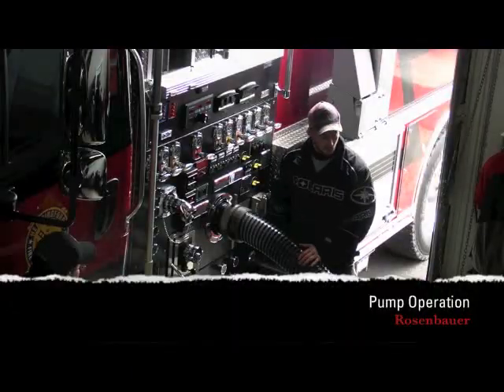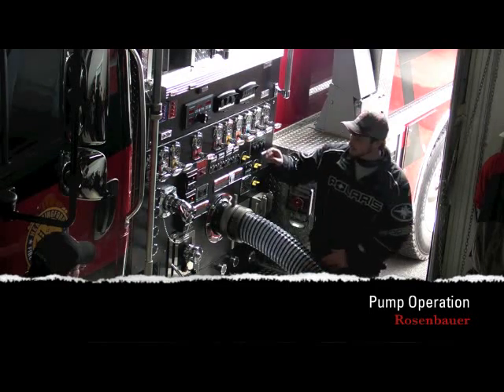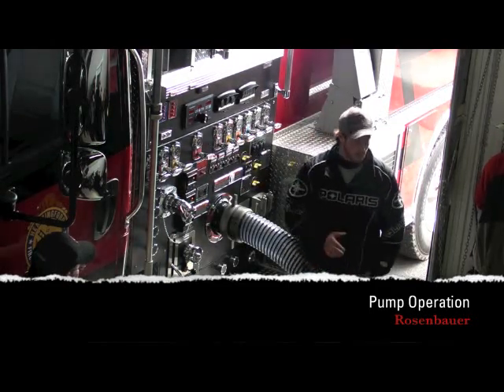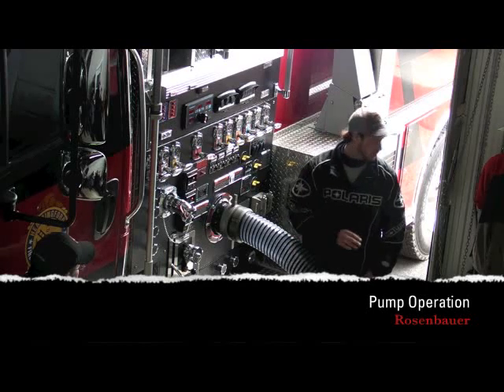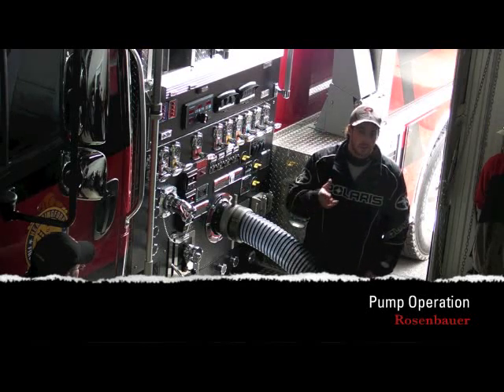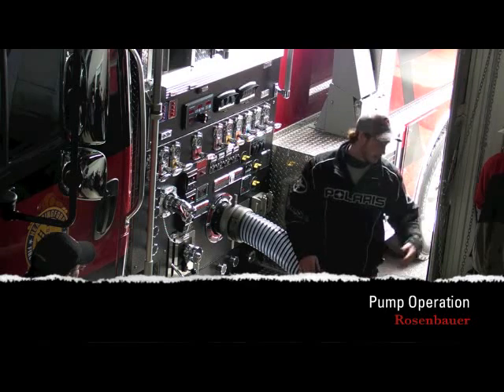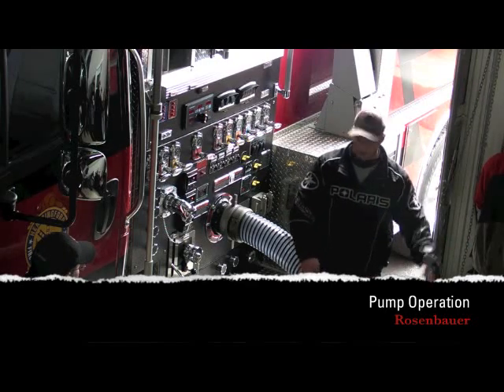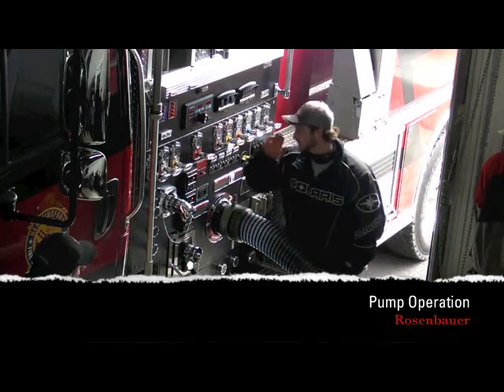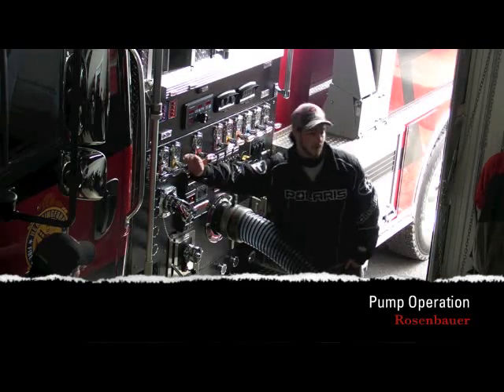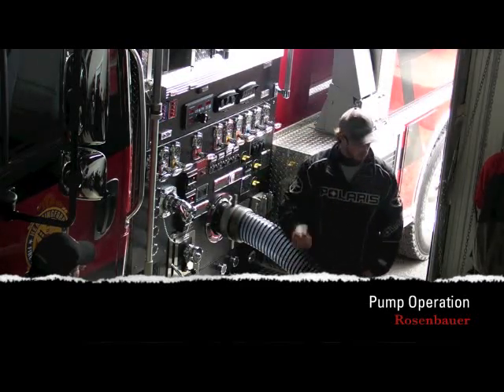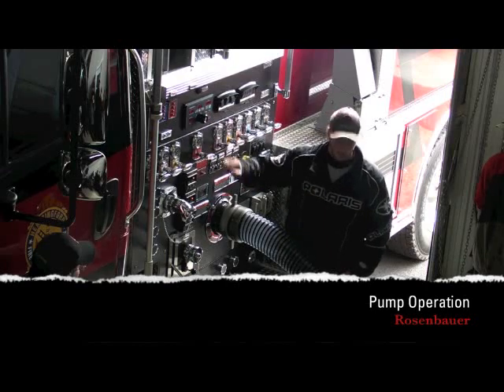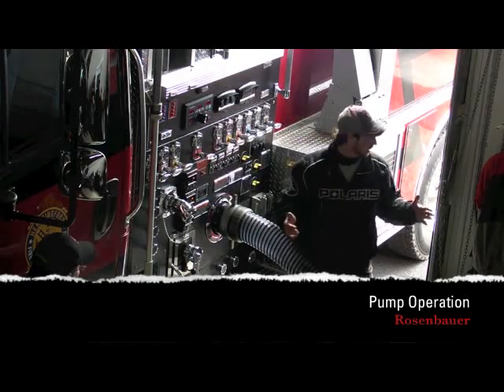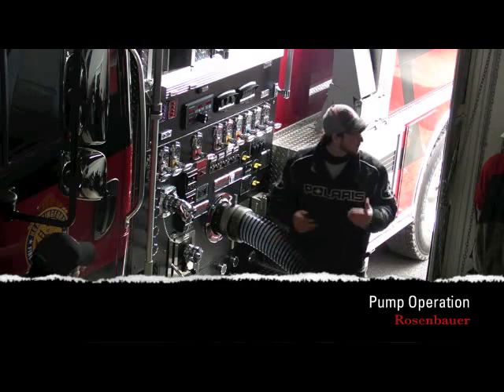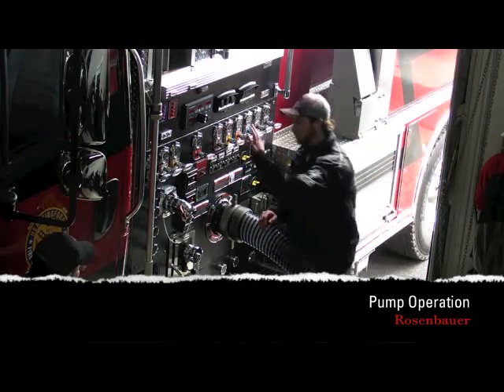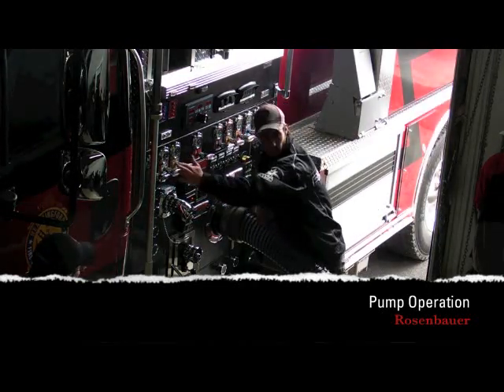The high pressure and low pressure pump work together, okay? So if I want 600 psi here, the high pressure side can go up to 600 psi. On the low pressure side, you guys will use maybe 125, 130, according to your needs. So if I want 600 here and keep it at 125, the master pressure always rules. So for my 600, I'll have to crank it wide open. What I'll do is crack this one. It's as simple as that. You always have to crack the lowest pressure you want. So you give yourself the master pressure on this one, and then I'll crack what I want.